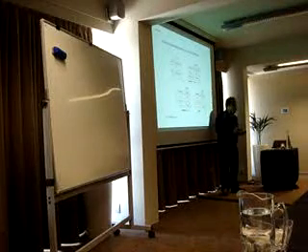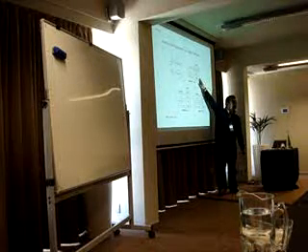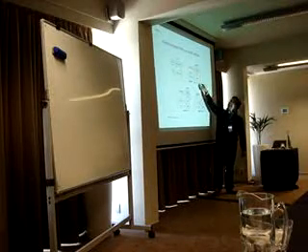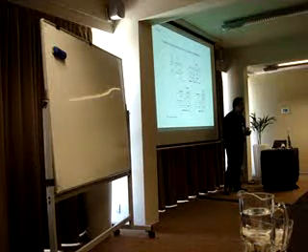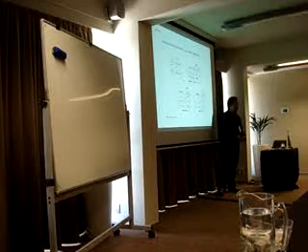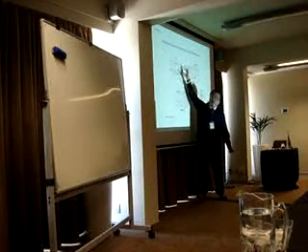Without going too much into detail, we have three tables here. They have some implicit data flow between them. So if you want to evaluate the tabular expression, you should always look at this one first. The final result for the trip depends on the lower trip and the higher trip. If either one of them trips, then you will trip eventually. Otherwise, you will say not trip. And we also have an assumption here, just to say that this region is non-overlapping.